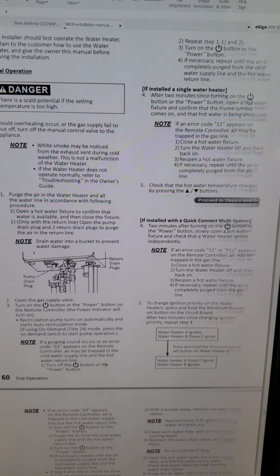This means there's something wrong with your recirculating system. If I turn the recirculating off, the error does not appear. So this is a recirculation circuit problem, not a problem with the main cold water in and hot water out operation. In other words, something is wrong with the recirculating circuit.